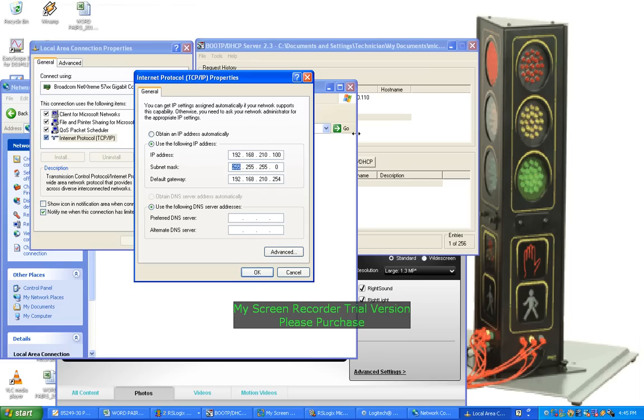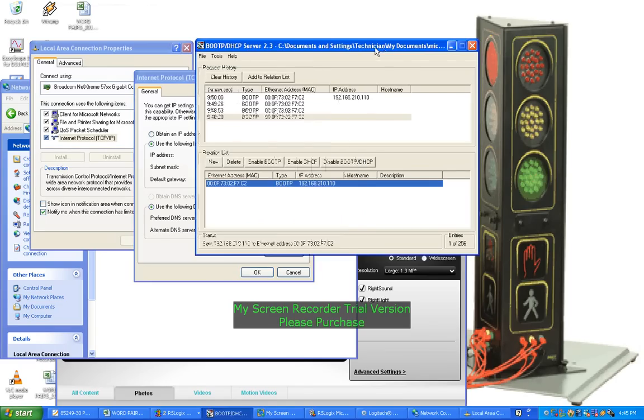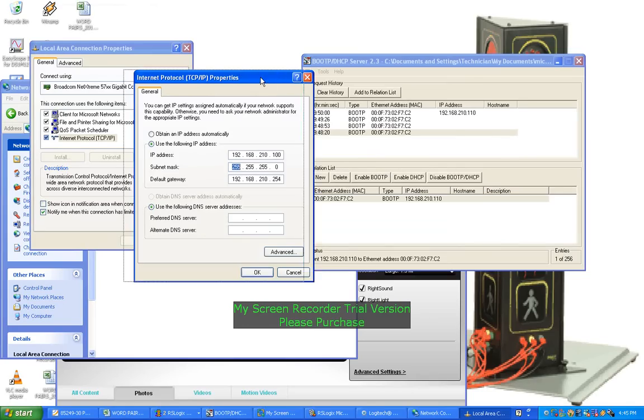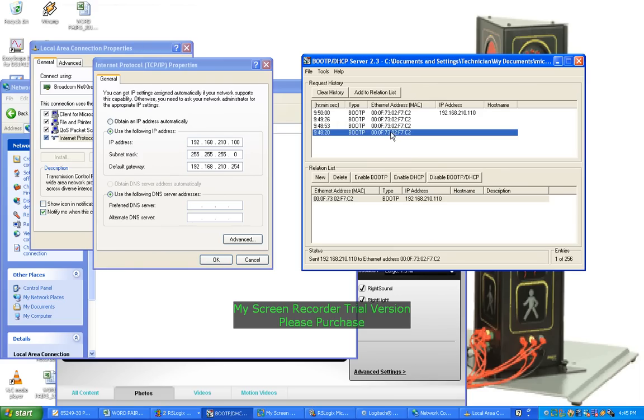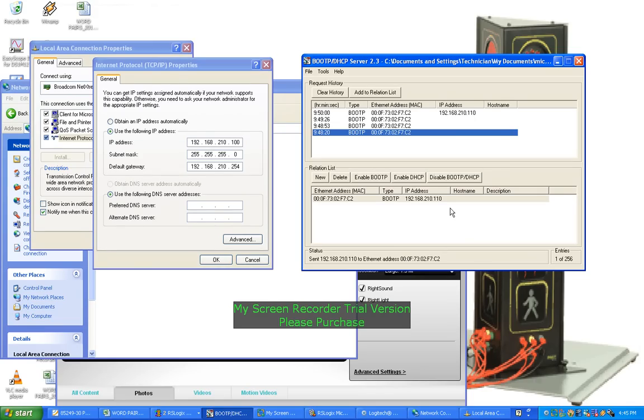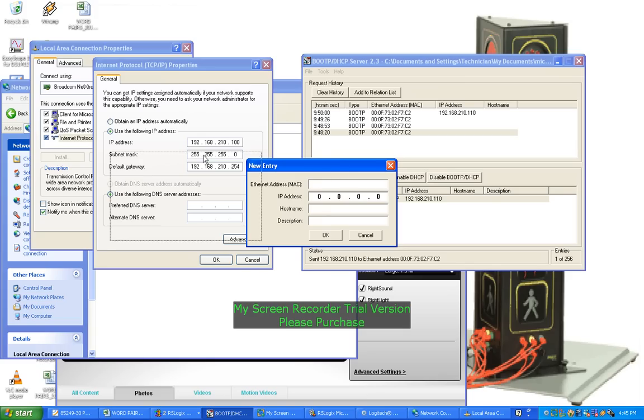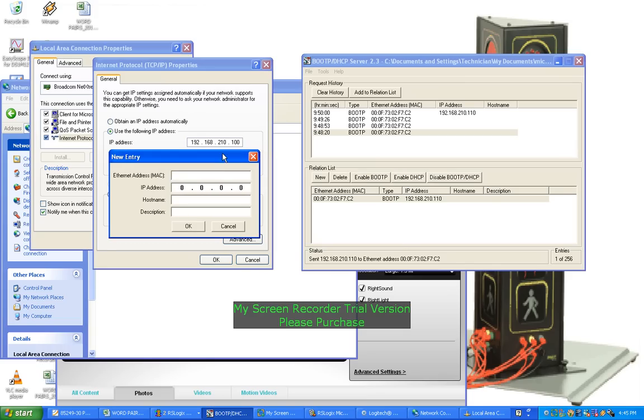So now if I go back to this program from Allen-Bradley, when you initially run this program, it will actually find what's known as a MAC address of the device that it's attached to. Now what you do is you set up a relationship here. You have to give this device an IP address so that they can begin to communicate with the computer. So you select New, and then you type in the MAC address which is given to you up here, and then you give it the IP address that you want this device to have.